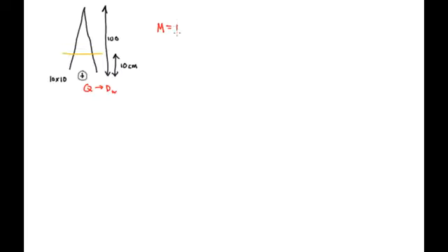All right, so ultimately you want this real reading M, but what you measure is M raw. I'm going to call it that; it's what actually comes out of your electrometer. So you have to correct that with some factors. So first is a temperature pressure correction factor. Then there's an ion collection efficiency factor, P-ion. There's a polarity factor. That's whether you reverse plus or minus voltage. And then finally, there's an electrometer correction factor for the efficiency of the collection in the electrometer. So I'm going to go through each of these in turn.